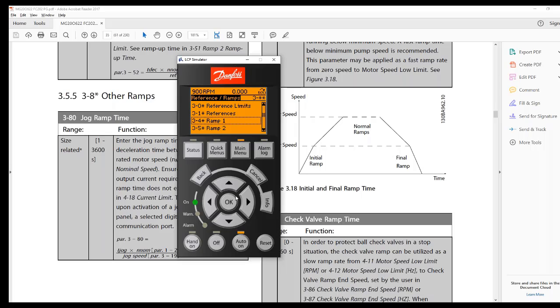There's a second ramp that has to be commanded, usually from a digital input or serially. It can be set to a second ramp if you need one. And then, as said, there's other ramps, application type ramps. If we're using jog, there's a ramp time just for that. There's initial ramp time, and like I said, the feature is off, so if I don't set anything, this will stay linear. But if I need to get up to minimum motor speed, say in half a second, I can set that. So then the ramp time will be up to minimum, and then the rest is full speed.